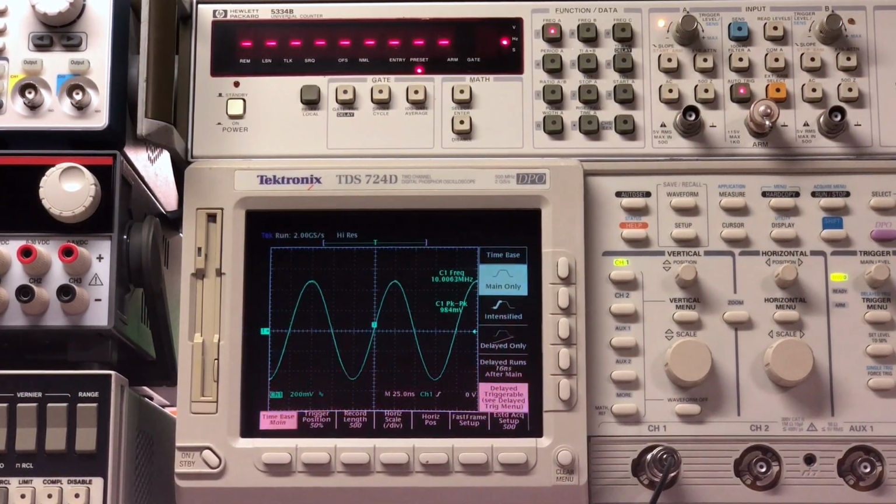So aside from that, we can see that the displayed waveform actually looks pretty reasonable. I don't see any serious issues. The displayed frequency looks very close to 10 megahertz. It looks like it's shifting around just a little bit there, but it is pretty close to 10 megahertz. The displayed peak-to-peak value is also very close to 1 volt. It looks like about 984, 992, so very, very close to that 1 volt peak-to-peak value.